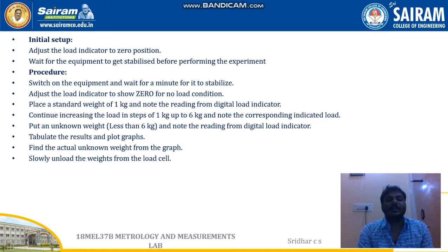Next, we need to place a standard weight of 1 kg, and take the reading from the digital load indicator for the weight of 1 kg. The next step is to place a weight of 2 kgs and take the corresponding indicated load. Similarly, we'll go up to 6 kgs. So we need to take 6 readings with the corresponding indicated loads.